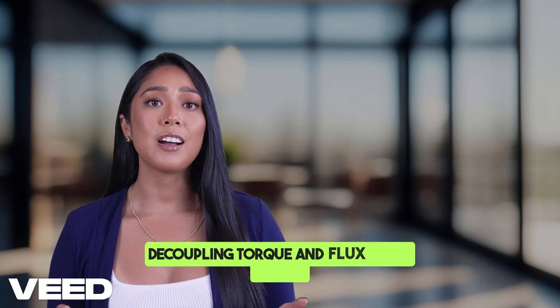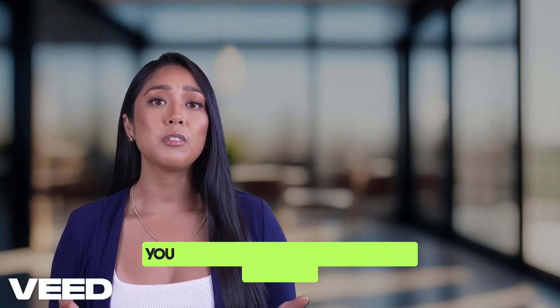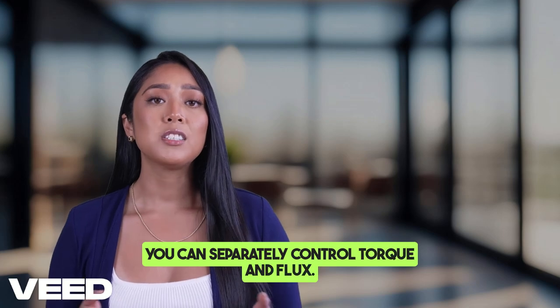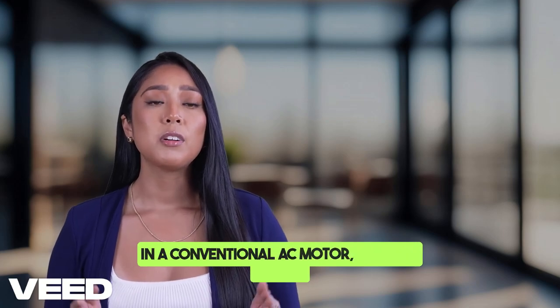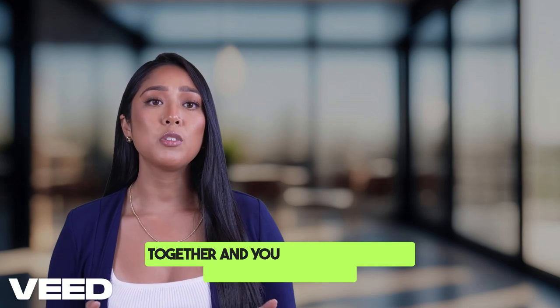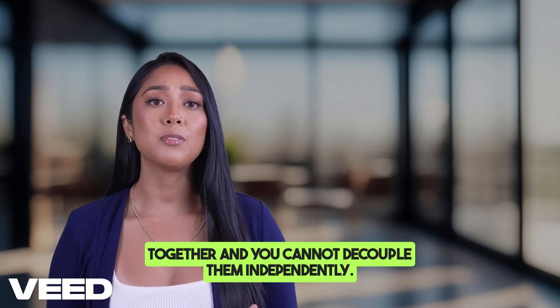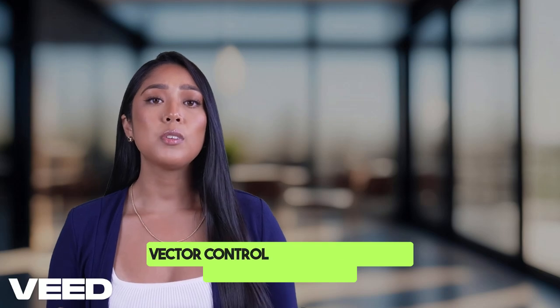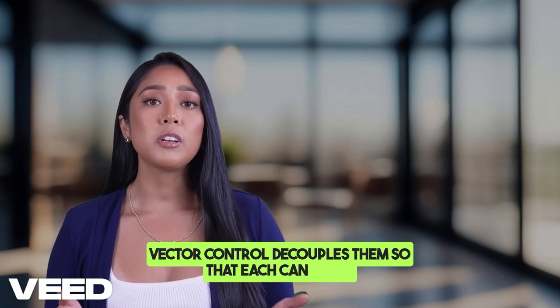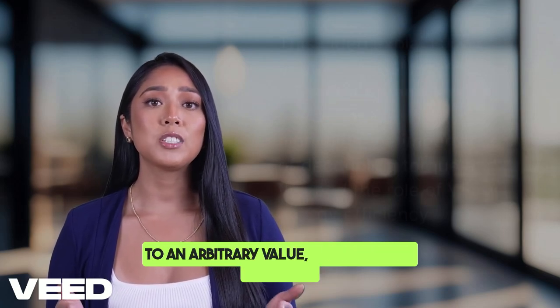Decoupling torque and flux. In a DC motor, you can separately control torque and flux. In a conventional AC motor, they are locked together, and you cannot decouple them independently. Vector control decouples them, so that each can be set to an arbitrary value, similar to in a DC motor.